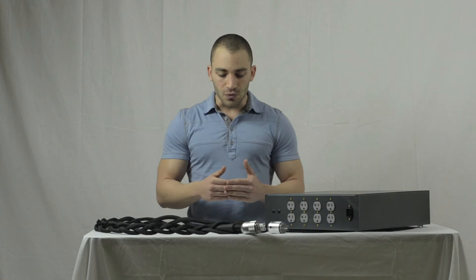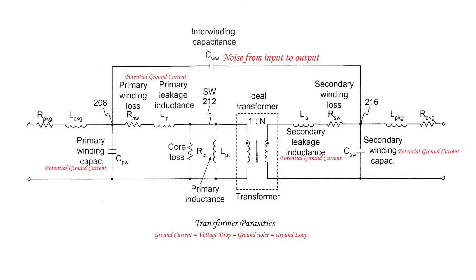The next type you'll see in a lot of newer conditioners are transformer-based — either isolation transformers, regenerators, or balanced power — and there are a lot of issues that I see with transformer-based conditioners. The first being parasitic capacitance, which is leakage capacitance coming from between the windings, meaning you have noise passing through the transformer that's not being isolated. Better manufacturers will specify the leakage currents and parasitic capacitances on their windings, and that's an important thing to pay attention to in terms of the effectiveness of that filter.